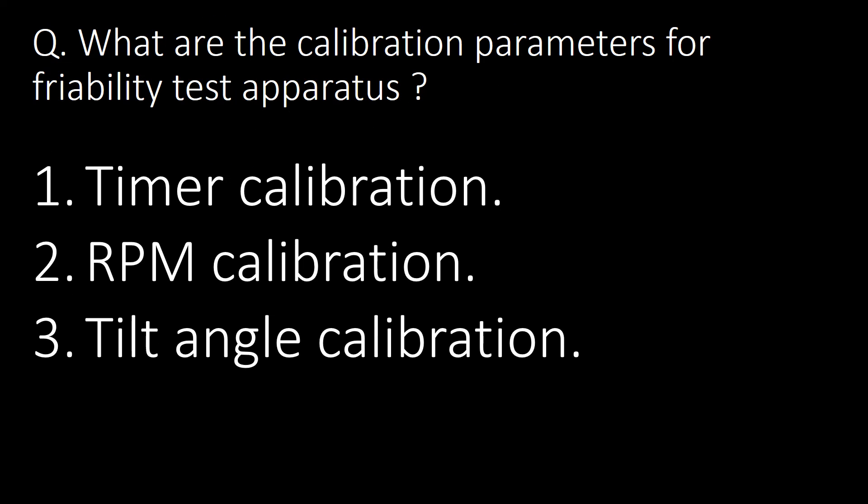What are the calibration parameters for the friability test apparatus? Following are the 3 important parameters that should be calibrated: first, timer calibration; second, RPM calibration; and third, tilt angle calibration.